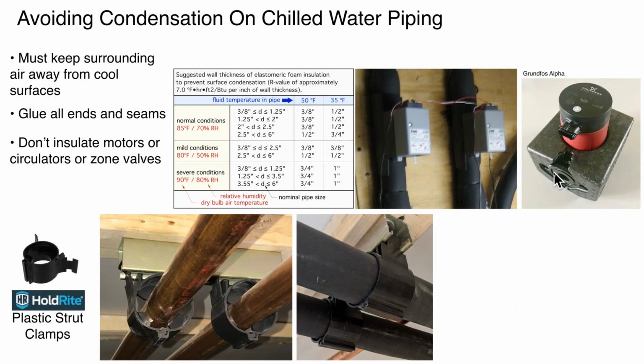So when you put this together, make sure you use some type of a sealant, probably silicone caulk would be good. If you're wondering how much insulation you need, for most applications, 3/8 to 1/2 inch elastomeric foam is adequate. If you're in a tropical situation, 90-degree temperatures, 80% relative humidity, and you're dealing with some of these different nominal pipe sizes, manufacturers are recommending 1 inch thickness.